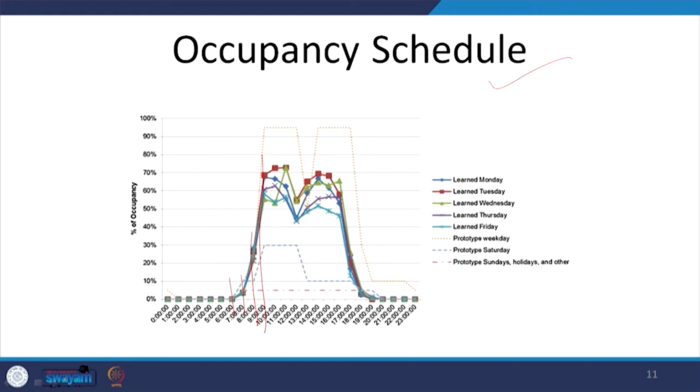Now, this is the actual. When we are calculating and estimating the performance of the building, we will assume the occupancy to be higher, somewhere close to 90%. Sometimes, for example in buildings like hospitals, the occupancy may be taken as much lower, at 75%. When we are talking about hotels, the occupancy may be taken even lower, at 60%. So, depending upon the use and type of the building, the occupancy schedule will vary.